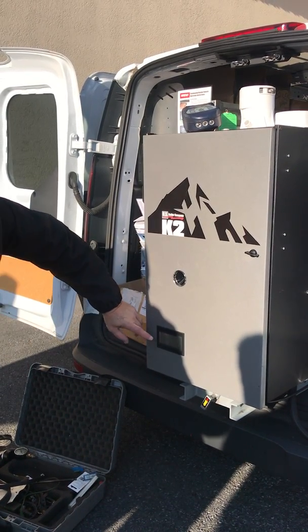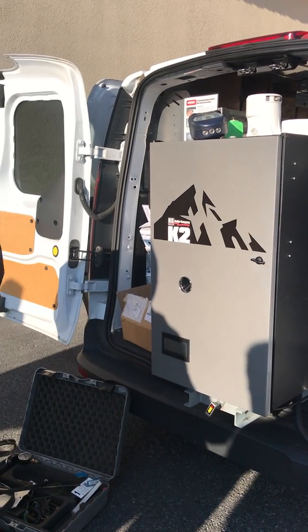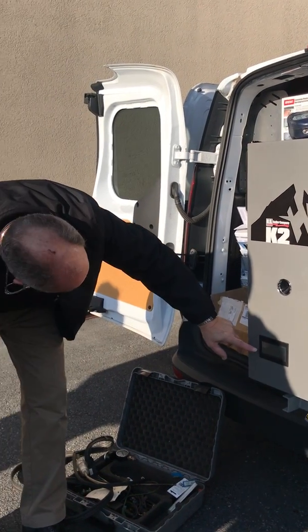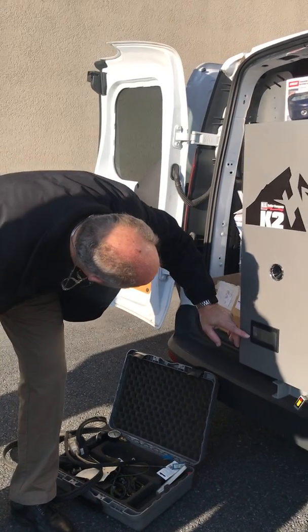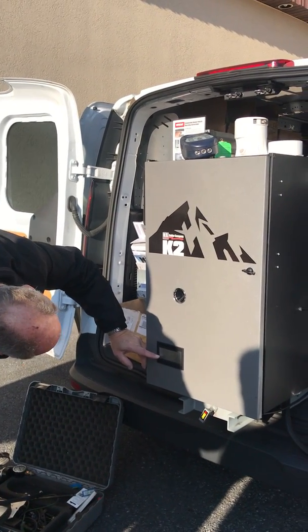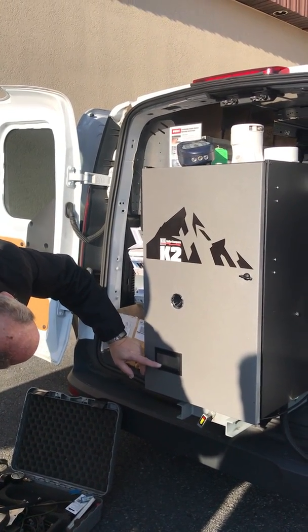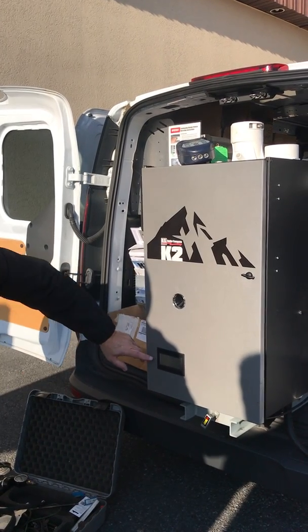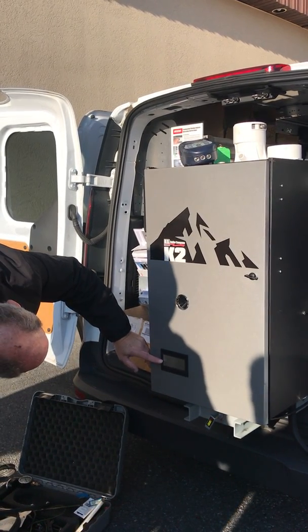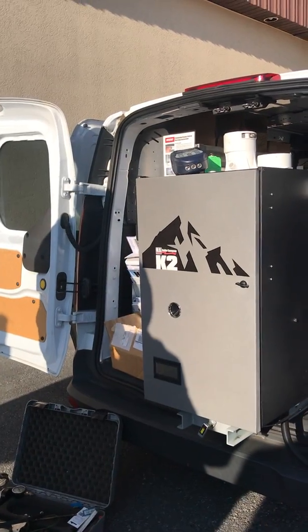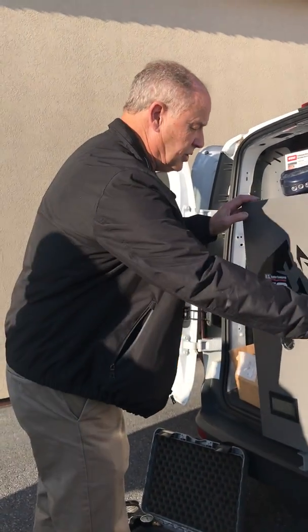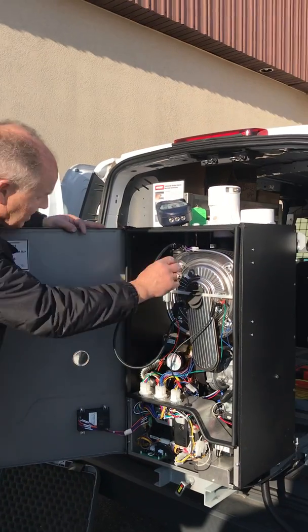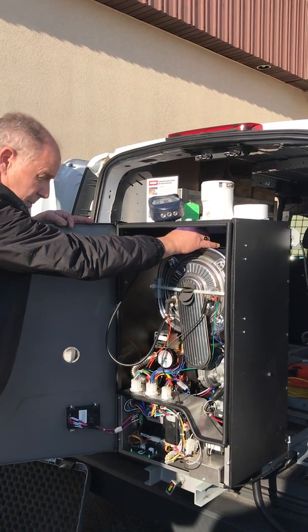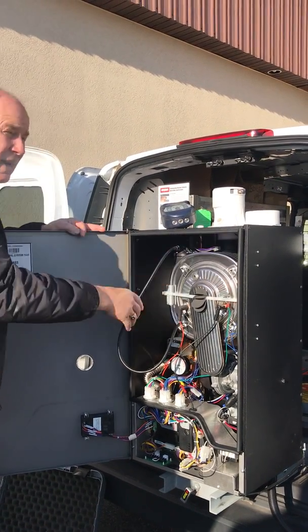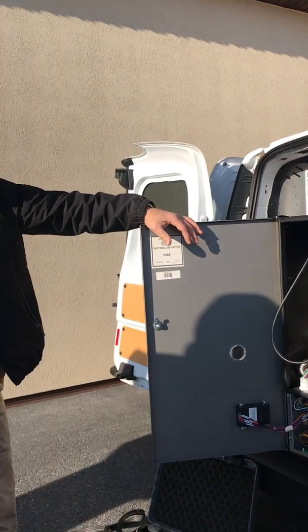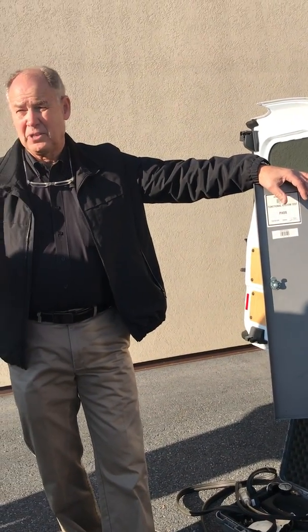And now it has 3 that I can actually put my sensor faults. And it actually goes through and it actually tells me that my outdoor sensor's missing and I have my header sensor. Oh, not the header sensor. I actually have the stack sensor. So this actually looks at the exhaust temperature. It's doing 2 things. One, it's going to protect so that if we end up having a problem that it gets overfired and my stack temperature goes up, we don't want the stack melting. Right. So it protects us, it shuts off.